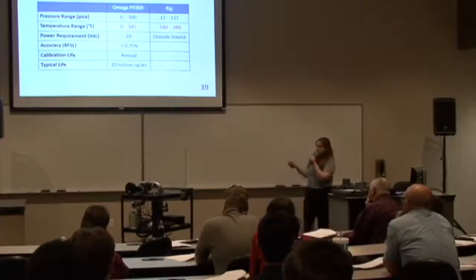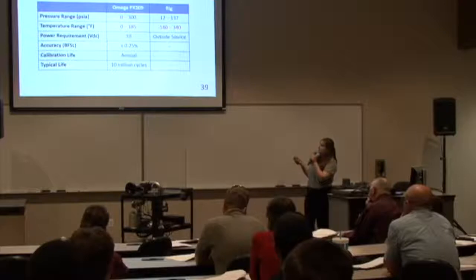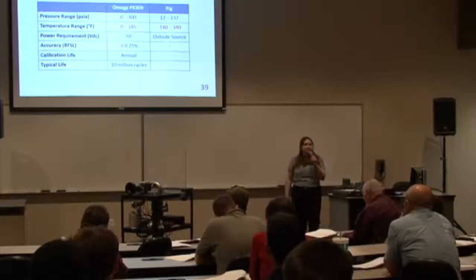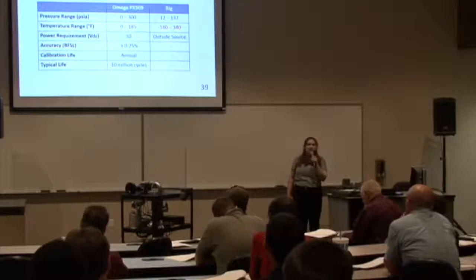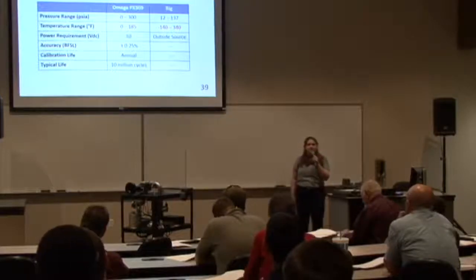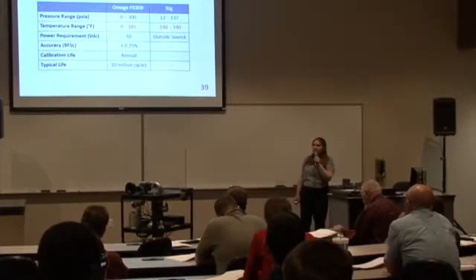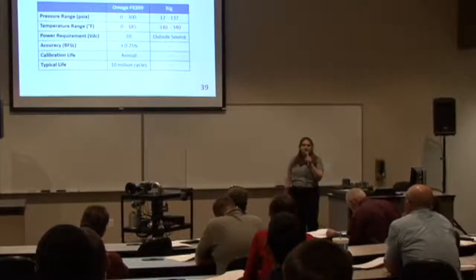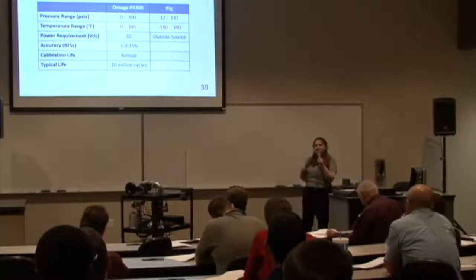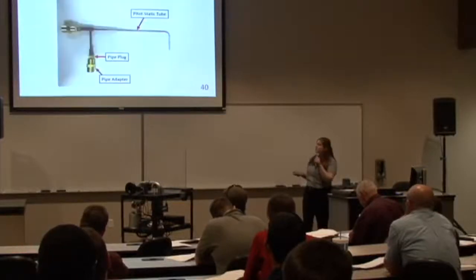As you can see on the table, the only specification not met by the Omega PX309 is the temperature, as our calculations show the rig could reach negative 140 degrees Fahrenheit to 340 degrees Fahrenheit, which exceeds the operating temperature range of the sensor. In order to protect the sensors, we are using pitot-static tubes in the airflow. This way, the pressure transducers can get the pressure information from the pitot-static tubes without being directly exposed to the extreme temperatures in the airflow.